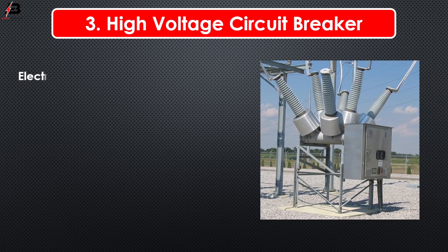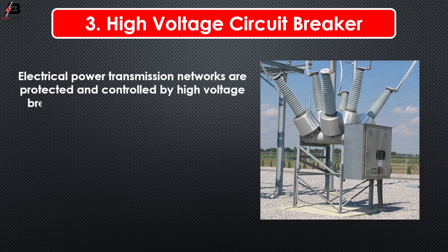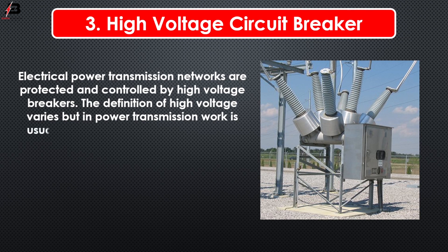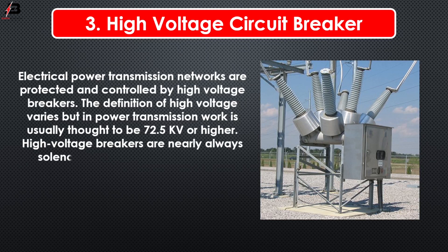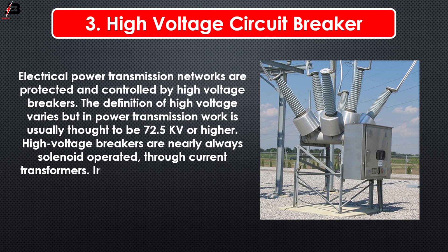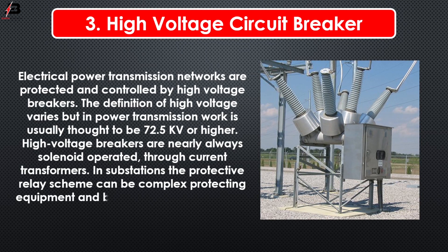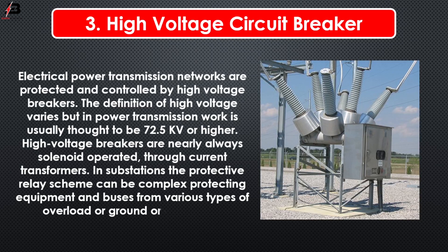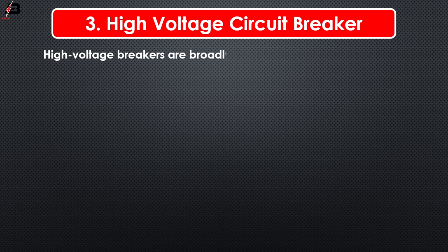High voltage circuit breakers. Electrical power transmission networks are protected and controlled by high voltage breakers. The definition of high voltage varies, but in power transmission work it is usually considered to be 72.5 kilovolts or higher. High voltage breakers are nearly always solenoid operated through current transformers. In substations, the protective relay scheme can be complex, protecting equipment and buses from various types of overload or ground fault. High voltage breakers are broadly classified by the medium used to extinguish the arc.